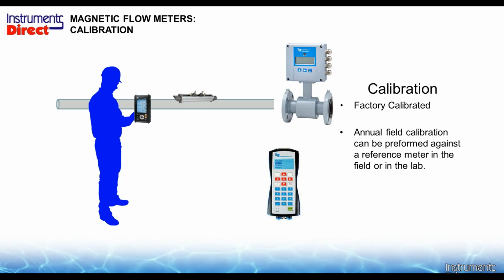For the most part, it's usually a paper trail because most of the mag meters, unless the overall application affects the electrodes and gums it up, pretty much is a solid state device there that really doesn't wander very much. So the overall accuracies don't really vary unless there's some application parameter that's affecting the performance of the device over a long period of time. So if you need an annual calibration, you can use tools in the field as the most economical way to take a look at it. When it ships out the door, you don't really have to worry about it because it's already calibrated and ready to go. If you need some custom calibrations or custom regulatory people, then those are special options that you can get for certification should you need those for your particular application.